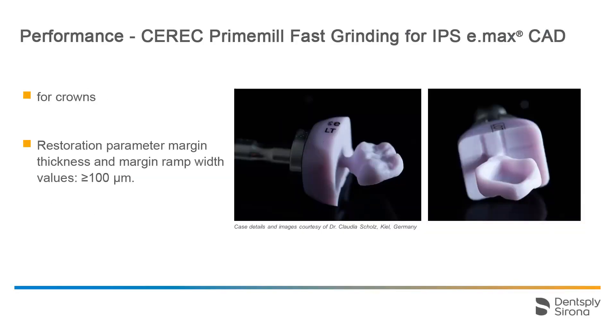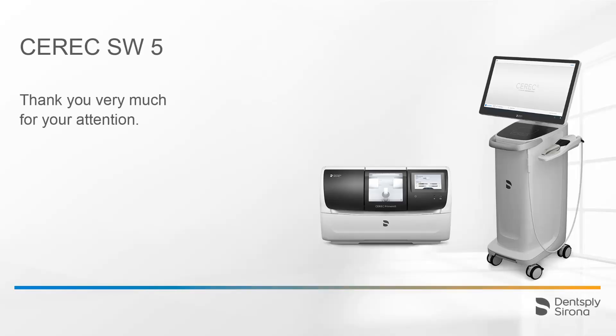Another update concerns fast grinding, which is now available for crowns with IPS eMax CAD. Please note that the restoration parameter for margin thickness and margin ramp width should be 100 micrometers or more. Thank you very much for your attention. We would like to wish you every success when working with CEREC.